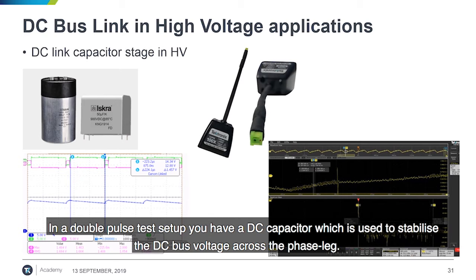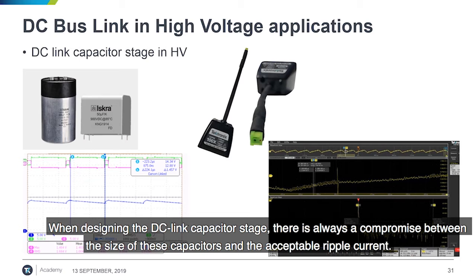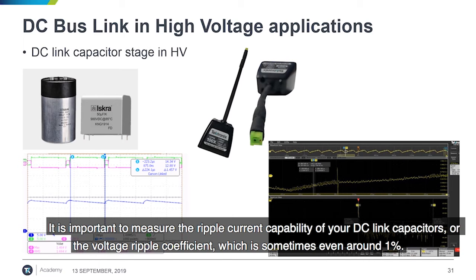In a double pulse test setup, you have for instance a DC capacitor used to stabilize the DC bus voltage across the phase leg. When designing the DC link capacitor stage, there is always a compromise between the size of these capacitors and the acceptable ripple current. So it's important to measure the ripple current capability of your DC link capacitors and the voltage ripple coefficient, sometimes talking about 1%.